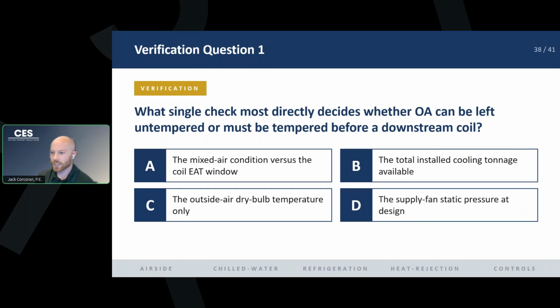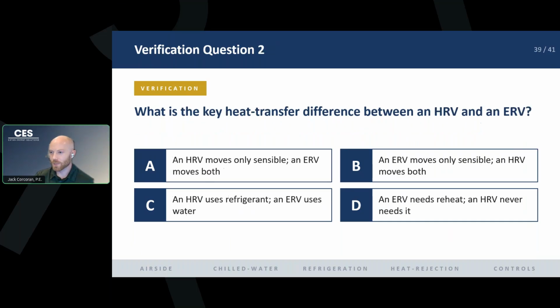And the answer is A, the mixed air condition versus the coil entering air temperature, right? So this is kind of inferred from what we talked about. If you are mixing your return air with the outside air fan, maybe that's your first check. You mix that 95 degree air, you find that tie line on your psychrometric chart when you mix them. If you can achieve a temperature that's removed enough moisture within our VRF entering air temperature range, then maybe you don't have to temper the air. But if you mix your return and your outside air and you're nowhere near the temperature you need to be before you reach the VRF, you're going to have to cool it down. DOAS is the solution. So on to the next question.